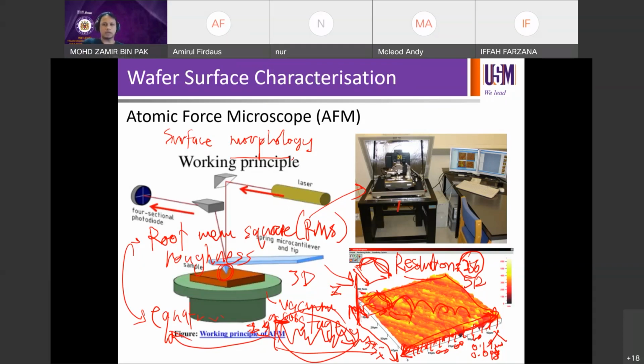From here you can see if your sample is very flat. For example, if you scan a bare glass substrate or a bare silicon substrate, where you haven't done anything on the wafer or on the glass, and you just scan the AFM, you'll see a very smooth surface with RMS typically below 3 nanometer. RMS roughness for a very flat surface is maybe about 3 nanometer or so, or lesser than that, 1 or 2. So that shows a very flat, very smooth surface.